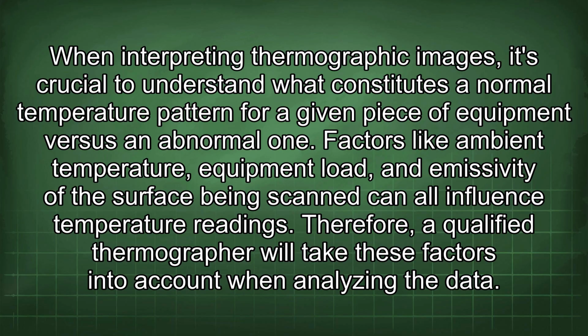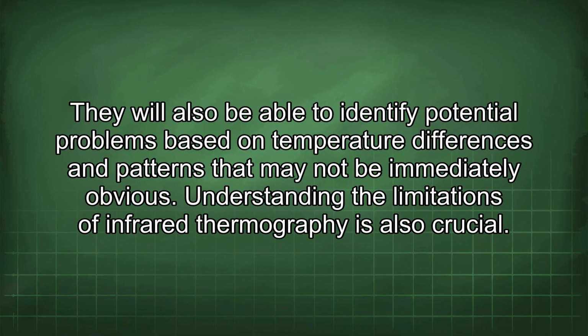When interpreting thermographic images, it's crucial to understand what constitutes a normal temperature pattern for a given piece of equipment versus an abnormal one. Factors like ambient temperature, equipment load, and emissivity of the surface being scanned can all influence temperature readings. Therefore, a qualified thermographer will take these factors into account when analyzing the data. They will also be able to identify potential problems based on temperature differences and patterns that may not be immediately obvious. Understanding the limitations of infrared thermography is also crucial.